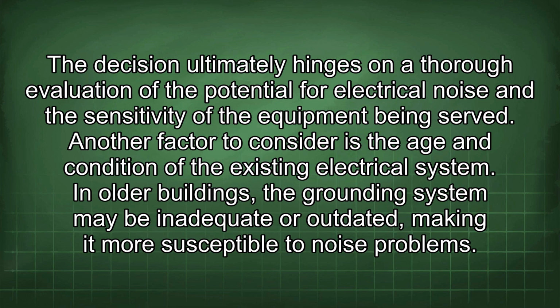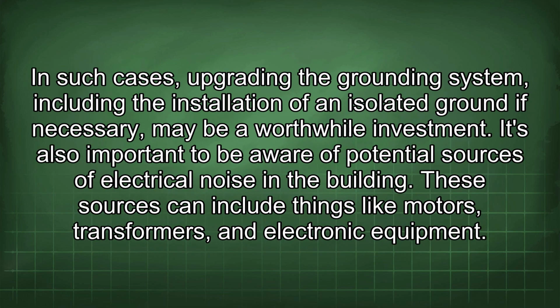Another factor to consider is the age and condition of the existing electrical system. In older buildings, the grounding system may be inadequate or outdated, making it more susceptible to noise problems. In such cases, upgrading the grounding system, including the installation of an isolated ground if necessary, may be a worthwhile investment. It's also important to be aware of potential sources of electrical noise in the building.